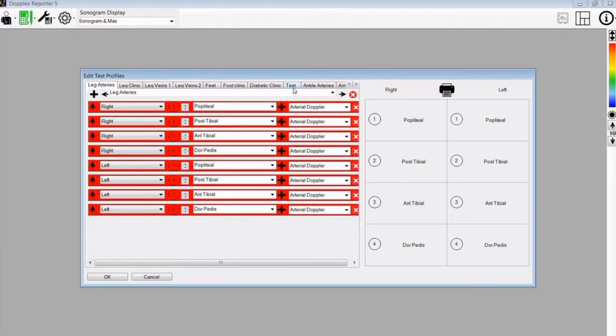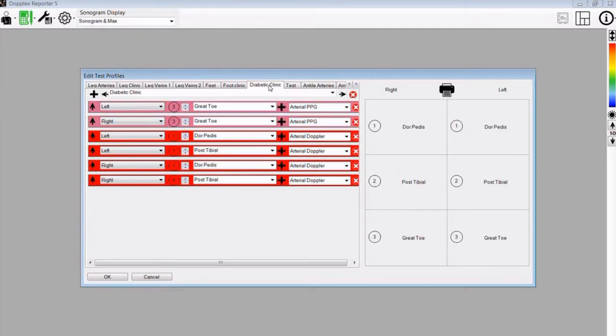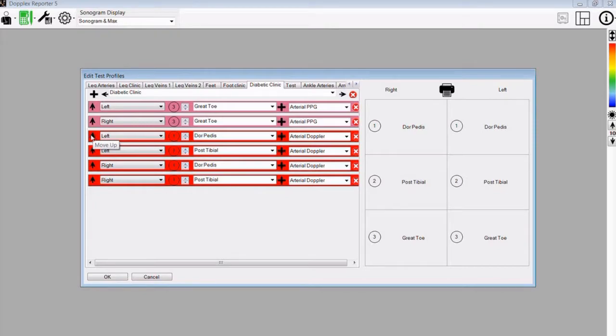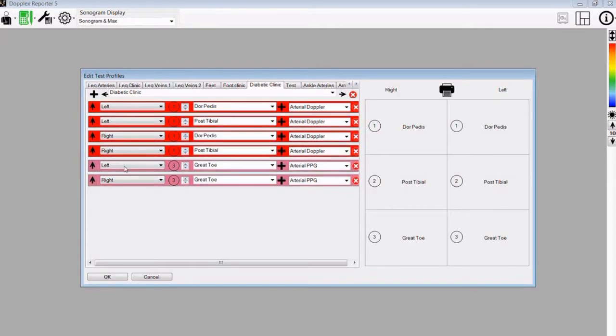Looking at edit test profiles again, there are mixed profiles. For instance, you can select a diabetic clinic. Here we have toes and vessels from the ankle, done in this order — toe pressures first and then ankle pressures. If you want to change the order, just move the vessel up to a different position. So we will be doing left dorsalis pedis, then posterior tibial, followed by right dorsalis pedis and posterior tibial, followed by left and right great toes. This is the profile we will use to demonstrate the next section.